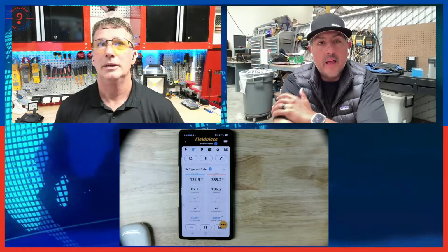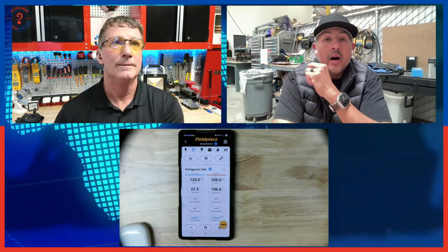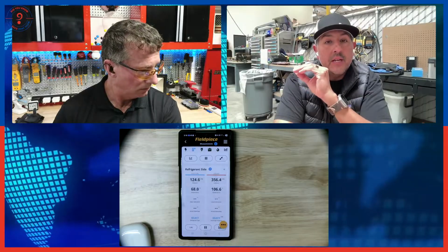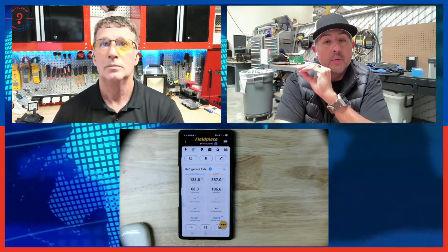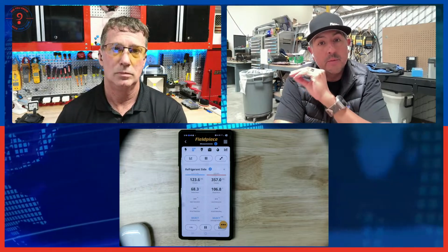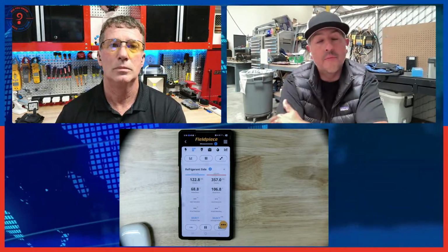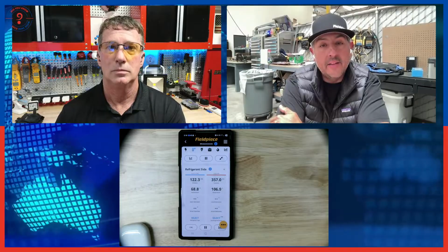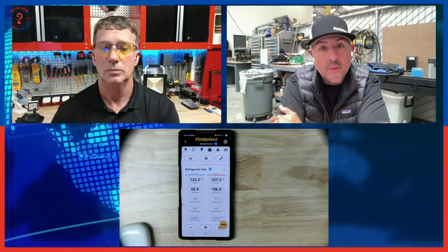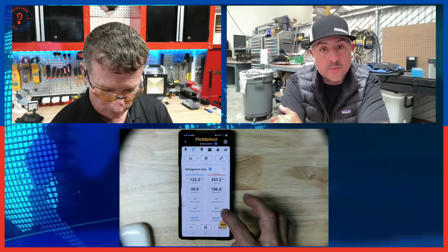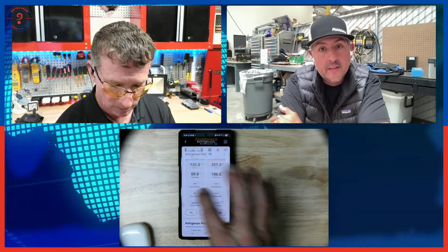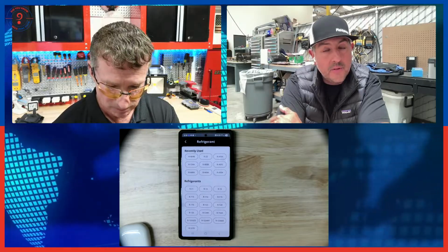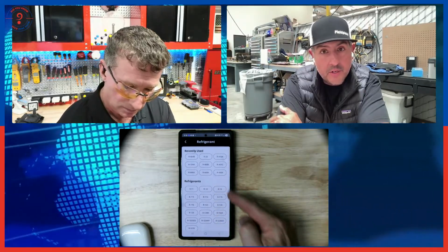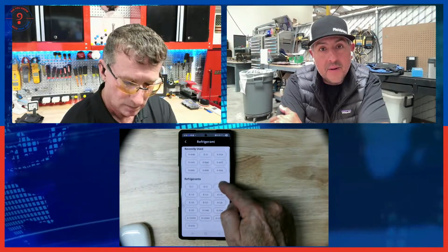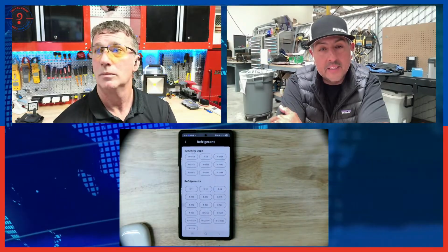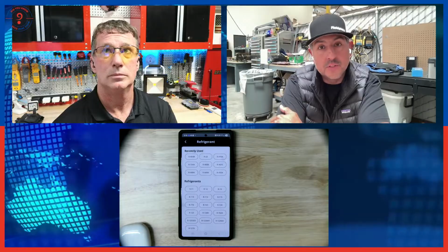Yep. Okay. All right. And so we have to remember that saturation temperatures are relative to the refrigerant type. So if we do not tell it what the refrigerant type is, it has no way to look up what the bubble and the dew points are. So let's go ahead and on the bottom of the suction column that says refrigerant type and it says select. So there we have a bunch of options to choose from. There's over 70 different refrigerants, including the new Class A2L refrigerants. But at the very top, you have a recently used section that is just going to populate with the refrigerants that you most commonly use.